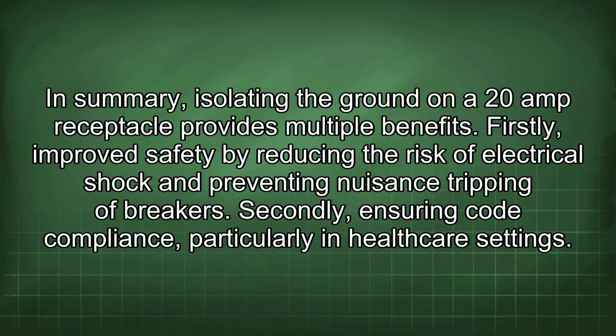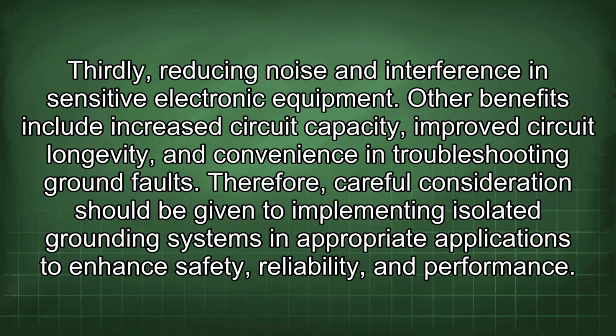In summary, isolating the ground on a 20-amp receptacle provides multiple benefits. Firstly, improved safety by reducing the risk of electrical shock and preventing nuisance tripping of breakers. Secondly, ensuring code compliance, particularly in healthcare settings. Thirdly, reducing noise and interference in sensitive electronic equipment. Other benefits include increased circuit capacity, improved circuit longevity, and convenience in troubleshooting ground faults. Therefore, careful consideration should be given to implementing isolated grounding systems in appropriate applications to enhance safety, reliability, and performance.